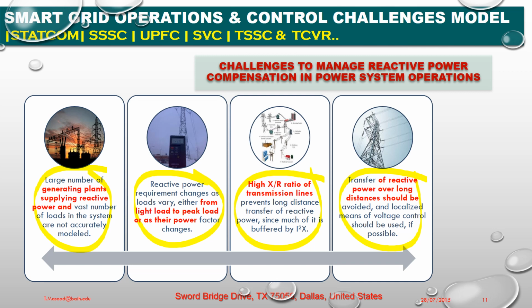So what is the first challenge? A large number of generating plants supplying reactive power and vast numbers of loads in the system are not accurately modeled. Number two, reactive power requirements change as loads vary, either from light load to peak load or as their power factor changes. Number three, the high X/R ratio of the transmission lines prevents long distance transfer of reactive power since much of it is consumed by I squared X. Number four, transfer of reactive power over long distances should be avoided and localized means of voltage control should be used if possible.